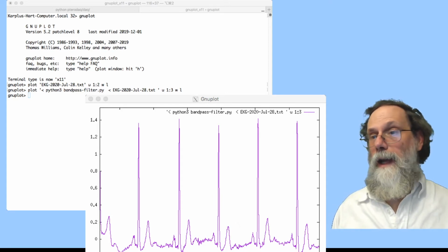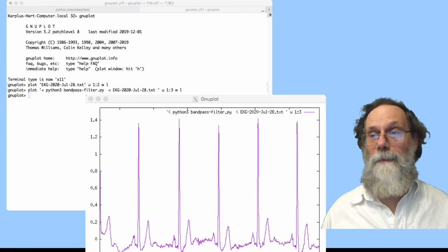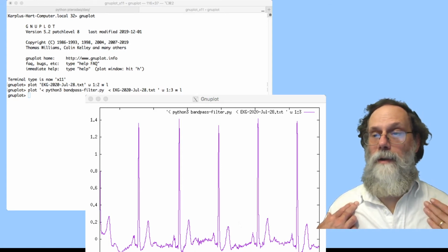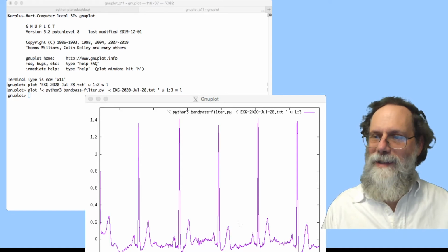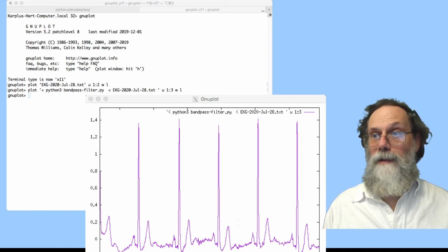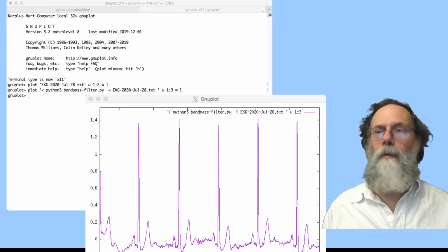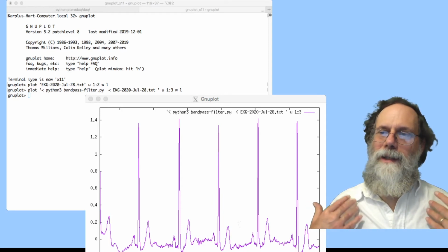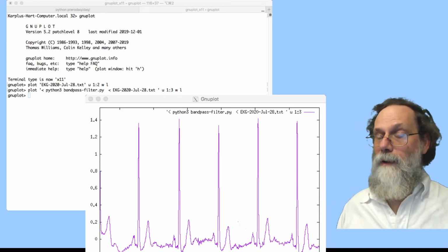And you can see that I have done amplification here so that I've got about what looks like 1.4 volts of signal here. Now, that's not really what you want to see in an EKG. What you really want to see is how many millivolts there were at the electrodes, because what amplification you've got in your amplifier is not really of interest to somebody interpreting a heart signal. So what they want is for you to correct for any offsets. They don't want stuff centered at 1.65 volts or something. They want it centered at zero, and they want it in units of how many millivolts it was out here. And to do that, you just have to take this signal you've got out of the filter and divide by the gain of your amplifier.